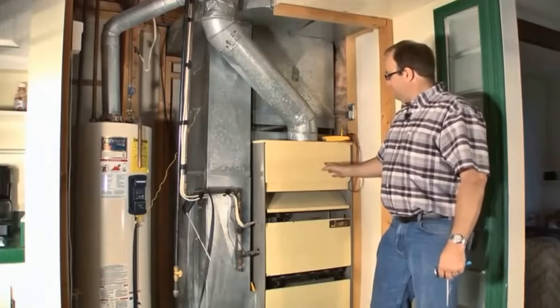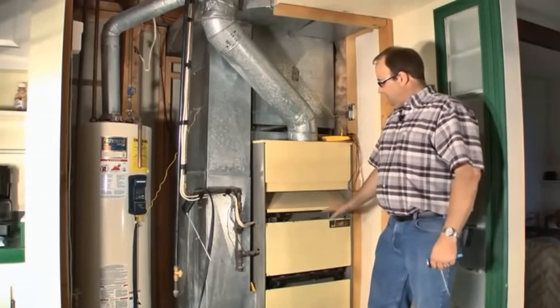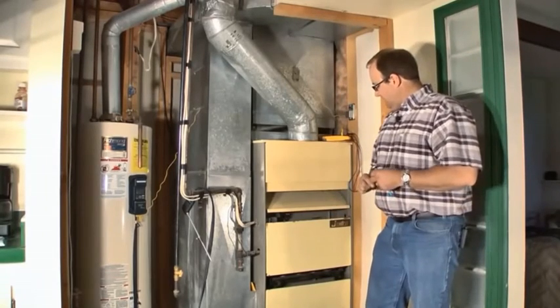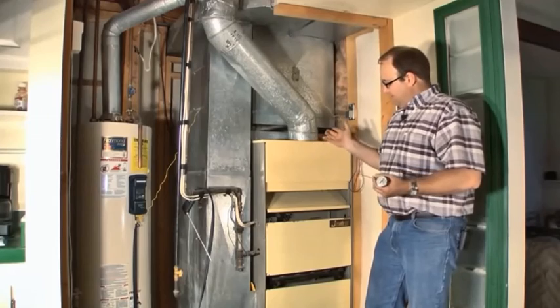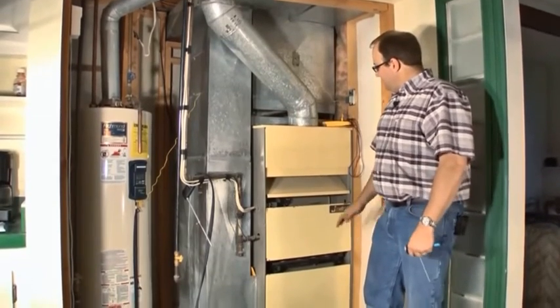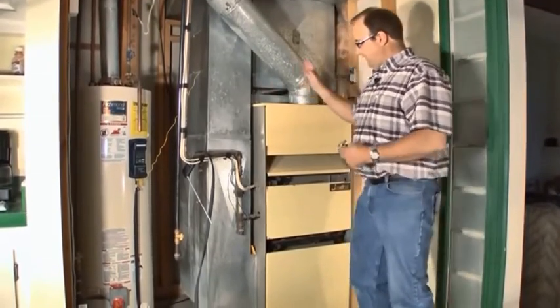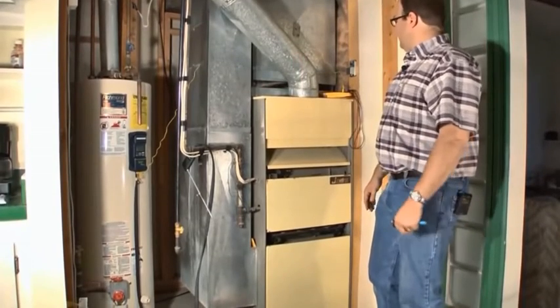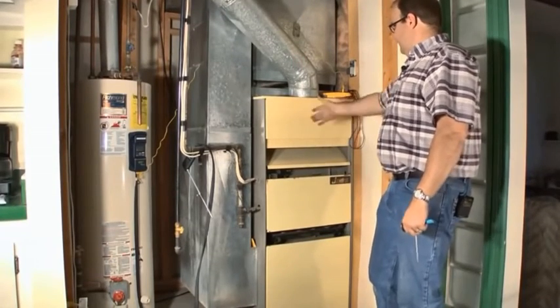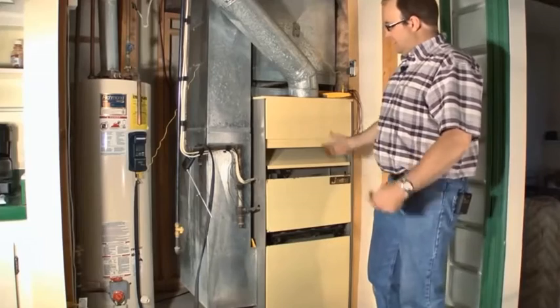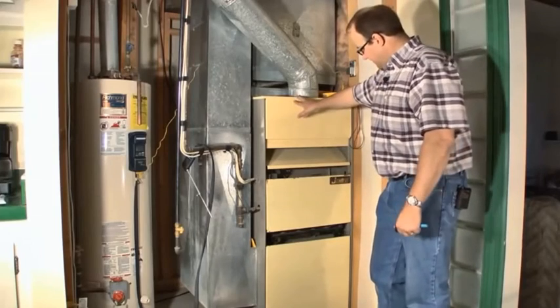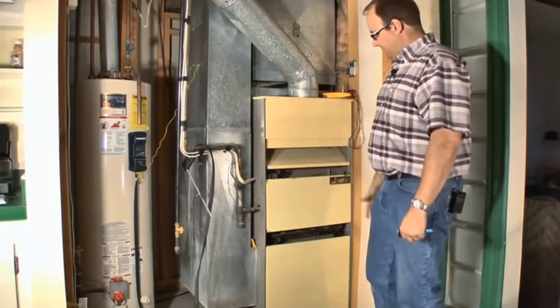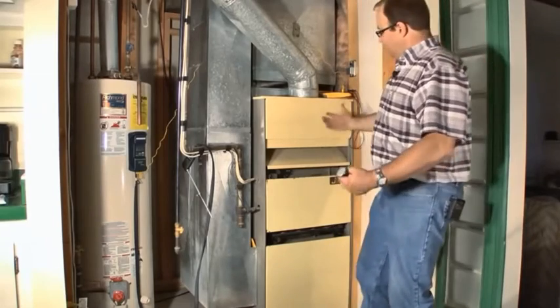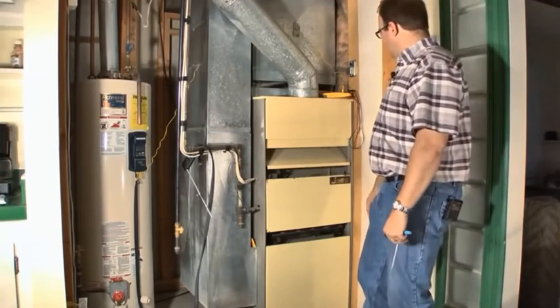Okay, a bit more about this furnace. One of the things we look for is how old the furnace is. I look for any clue that tells me how old it is. Based on this house, I know this is the original furnace installed in the house. I can tell just from experience. So it's at least 20 years old.